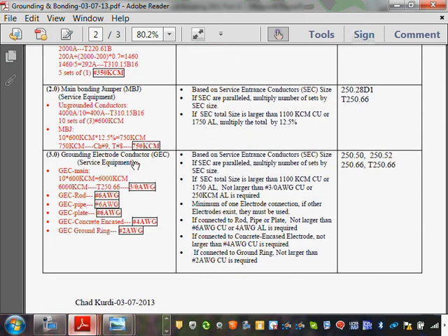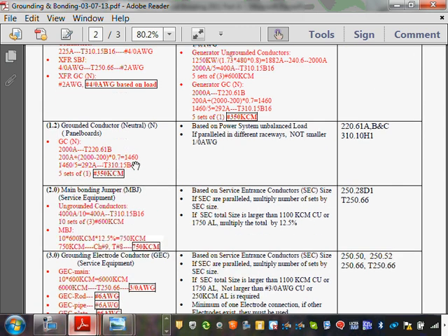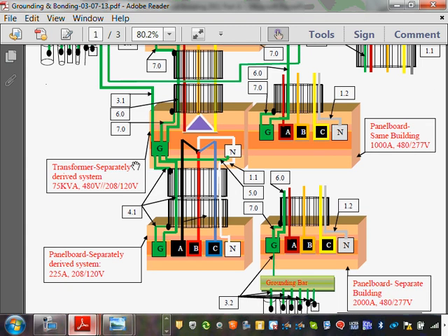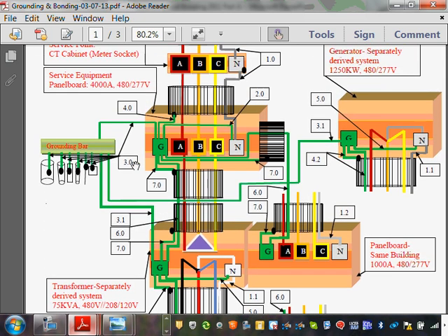Okay, so that's back to the grounding electrode conductor. Any comments, guys, about the grounding electrode conductor? Now, with all these routes that we did at the grounding, we grounded our building. We grounded our service. So if you guys go back, now my service is up a little bit. It is grounded, right? So now the enclosure, the boxes, the switchgear is grounded through these systems. My system is grounded, right?